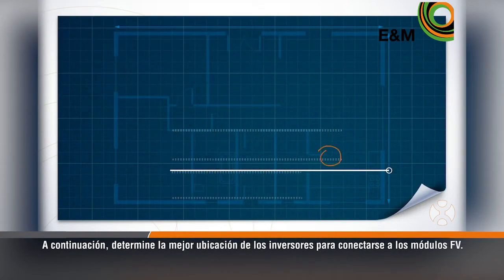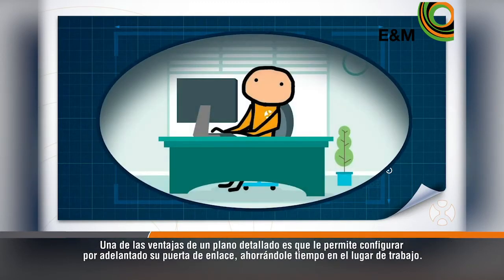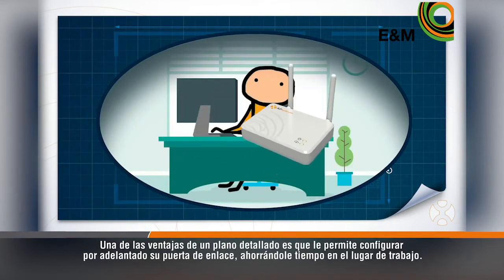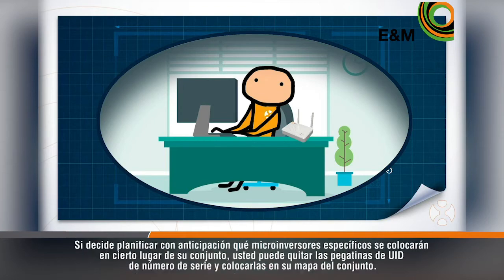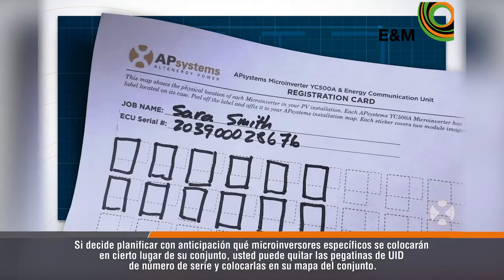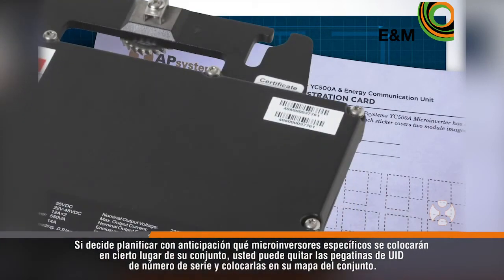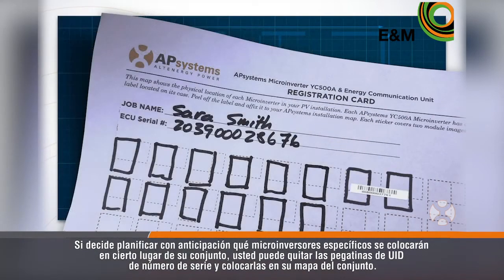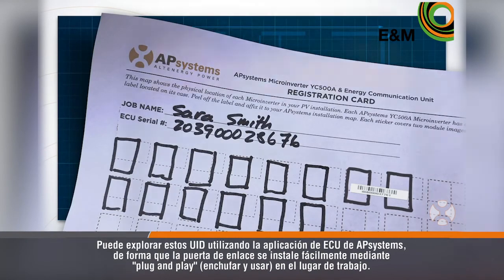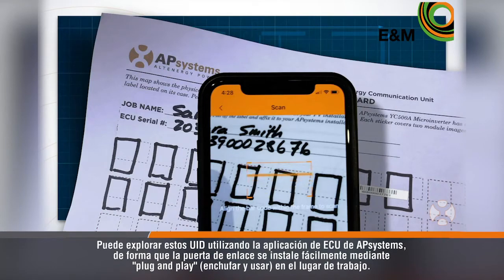Next, determine where the inverters can best be positioned to connect to the PV modules. One of the benefits of a detailed layout map is that it allows you to set up your gateway in advance, saving you time at the job site. If you choose to pre-plan which specific microinverters will be placed where in your array, you can remove the serial number UID stickers and place them on your array map. You can scan these UIDs using the APsystems ECU app, so the gateway is plug and play at the job site.